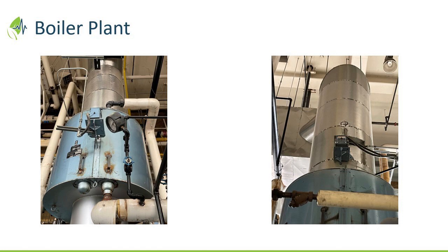Brent, what issues, what challenges did your operators have? And then we'll get to the draft damper, because you can point out where that is. But with this setup around the economizers, the draft dampers, that whole configuration, what issues did the operators have to deal with? Yeah, in particular, if the boiler's running efficiently based on the parameters that the operators can monitor, some of those things go beyond line of sight. And then it's an unfortunate waste of energy and resources.